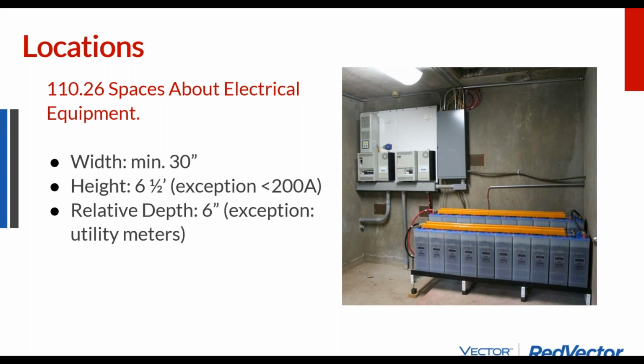Dedicated 6.5 feet, the doorway, like we talked about before. The depth is the one thing people get caught on. In this picture, there's an error, because to access the service panel, you would have to lean over the battery bank. In fact, that's a code violation. If you look to the left, there's panels that are maybe 4 inches deep, and another panel that's 6 inches deep. The code says, within that same vertical space, from one equipment to the next, if they're sharing the same vertical space, they have to have a depth that is uniform within 6 inches. No leaning over electrical equipment to work on other electrical equipment.